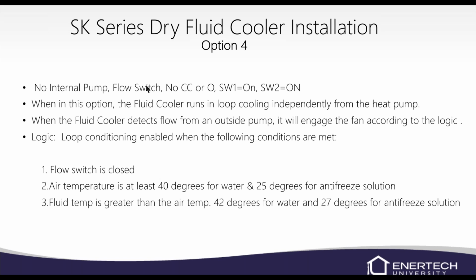Option 4, there'll be no internal pump, but you've got a flow switch, no compressor contactor or O. So that would be switch 1 on, switch 2 on. Basically, when in this option, the fluid cooler runs in loop cooling independently from the heat pump. So when the fluid cooler detects flow from an outside pump, it's going to engage the fan according to the logic. So loop conditioning enabled when the following conditions are met.